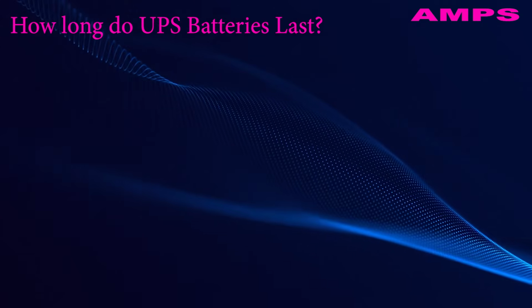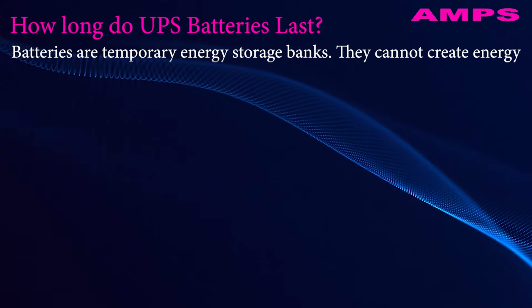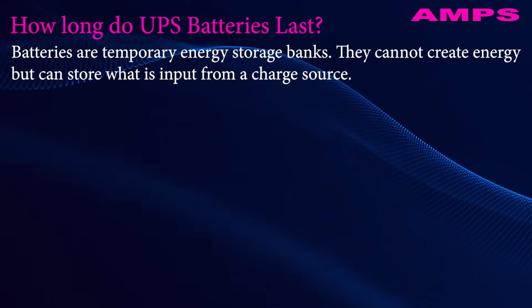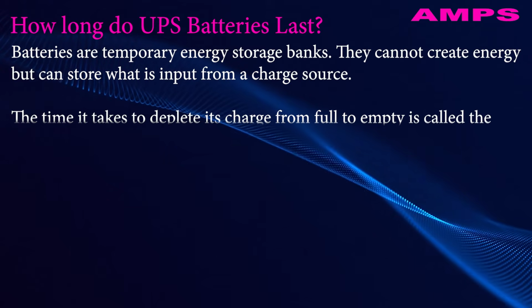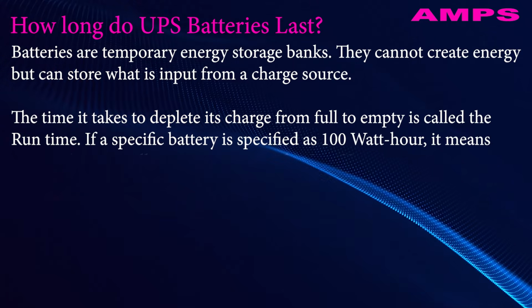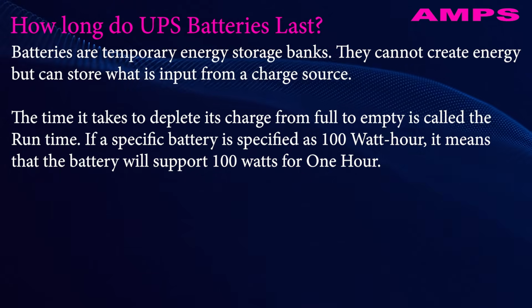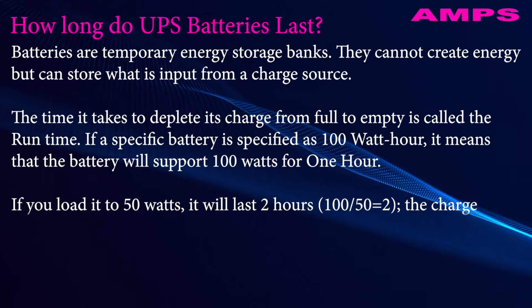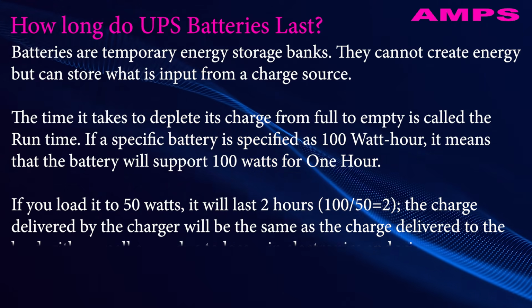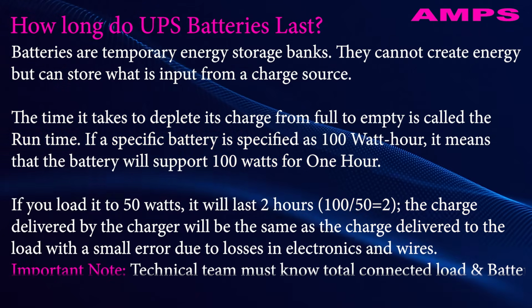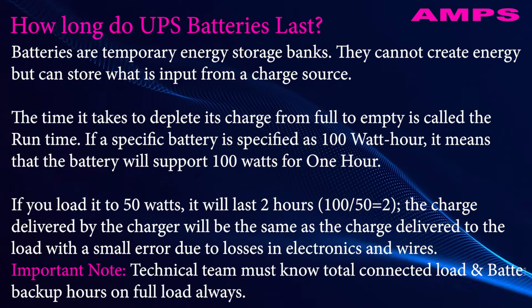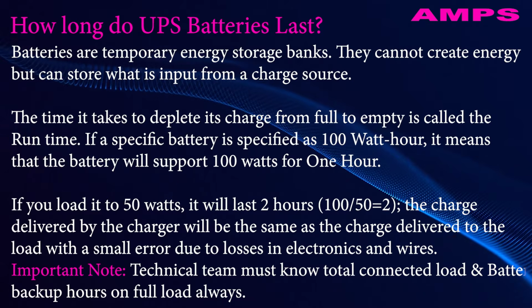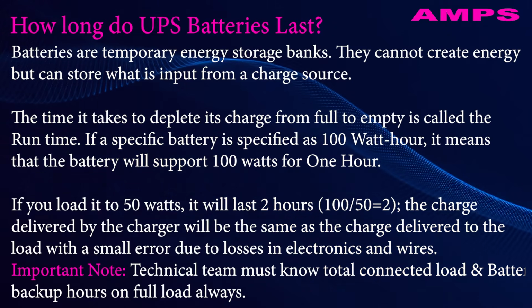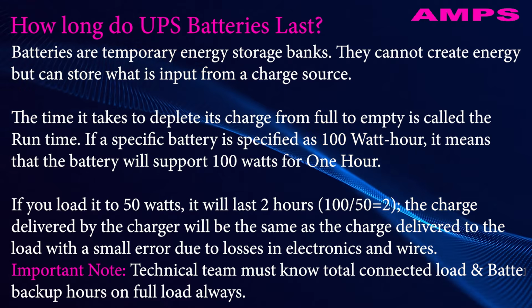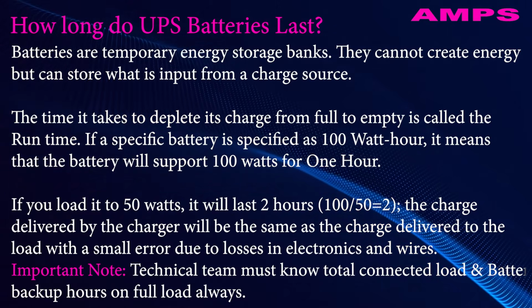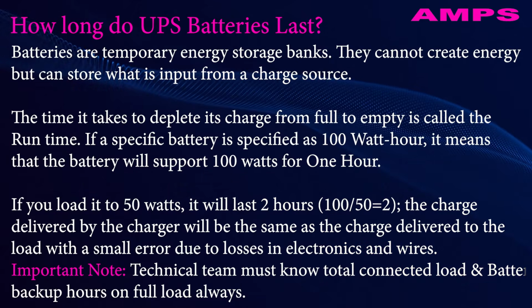How long do UPS batteries last? Batteries are temporary energy storage banks. They cannot create energy but can store what is input from a charge source. The time it takes to deplete its charge from full to empty is called the runtime. If a specific battery is specified as 100 watt-hour, it means that the battery will support 100 watts for 1 hour. If you load it to 50 watts, it will last 2 hours, 100/50 equals 2. The charge delivered by the charger will be the same as the charge delivered to the load, with a small error due to losses in electronics and wires. Note: the technical team must always know the total connected load and battery backup hours on full load.